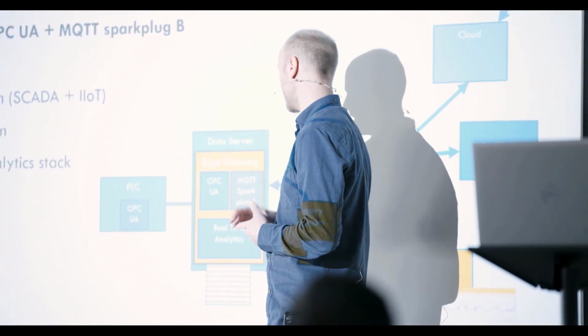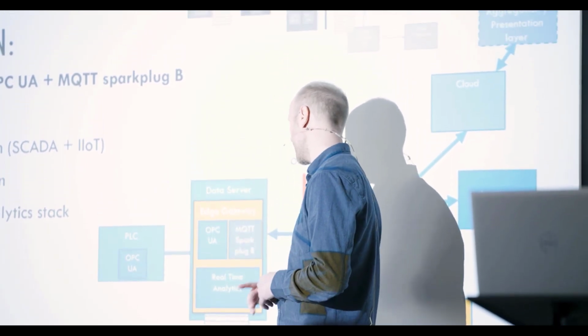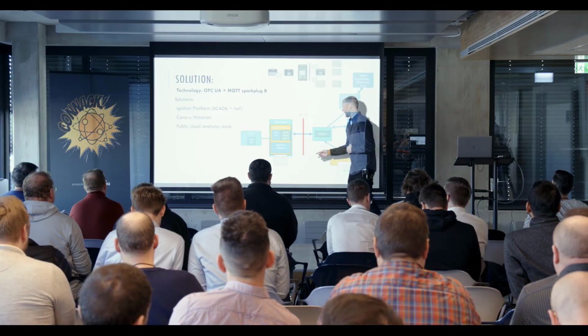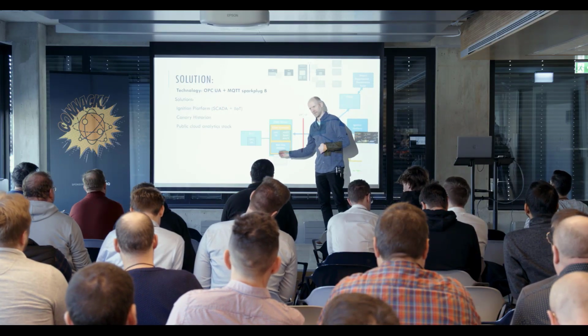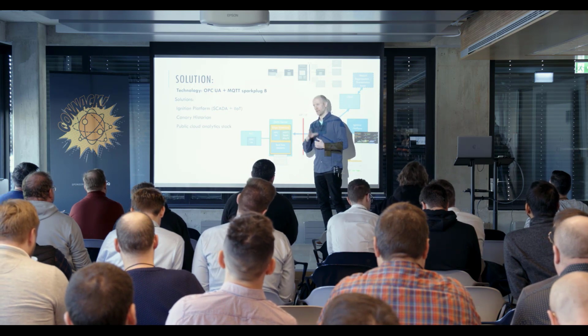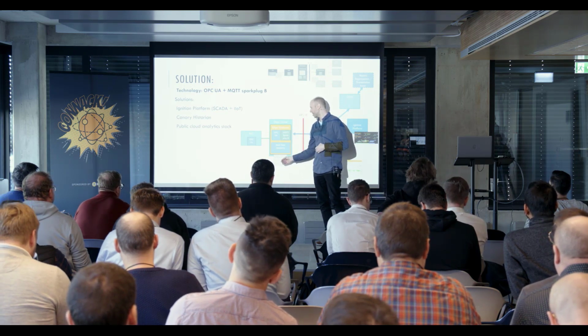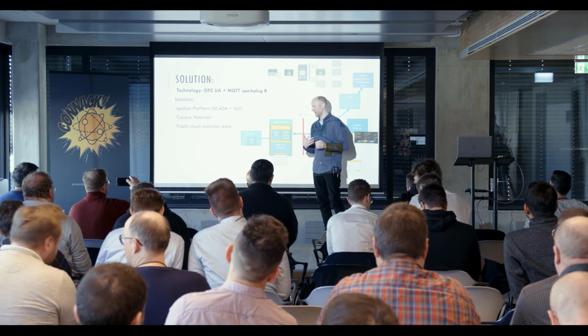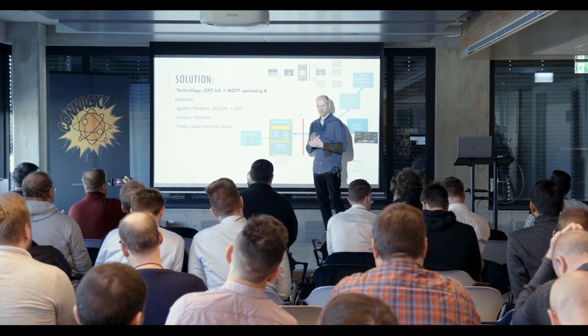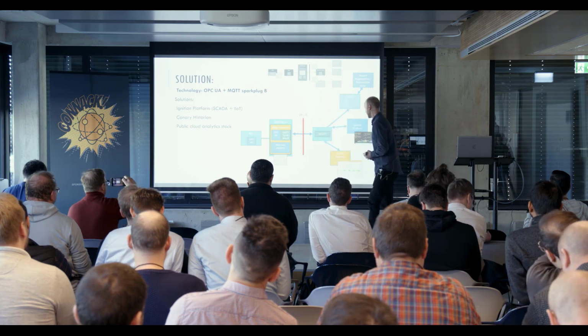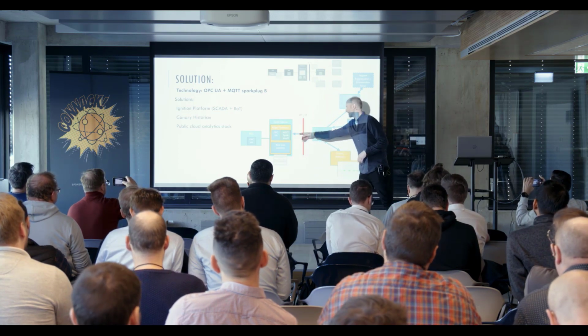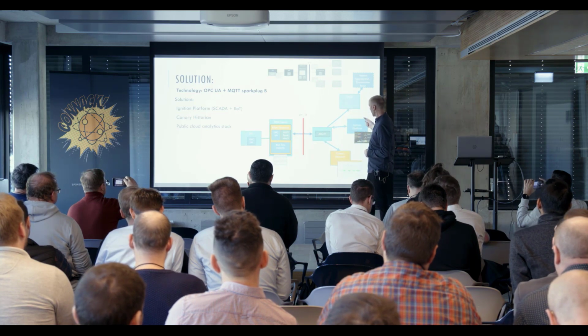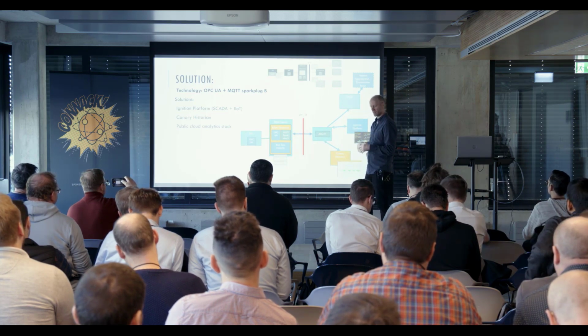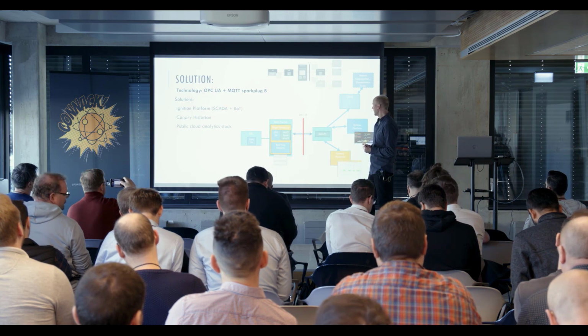On the edge we have an edge gateway which takes OPC UA and turns it into Sparkplug B, and then we do some real-time analytics if needed. That's our only place of configuration. There we get the data, transform or normalize it, and do some modeling. Then this data is sent to MQTT, and both the cloud - we have an Ignition platform and a Canary historian - can get this data.